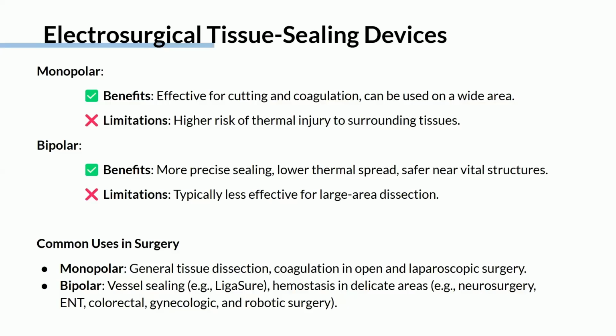Bipolar energy, on the other hand, is more precise because the current flows only between the two electrodes at the instrument tip, as we mentioned, meaning there's less thermal spread and safer application near vital structures. This type of energy is particularly useful and very frequently used for vessel sealing, and it is also widely used in neurosurgery, ENT, and robotic procedures as well. However, bipolar energy is in general less effective for large area dissection compared to monopolar energy.